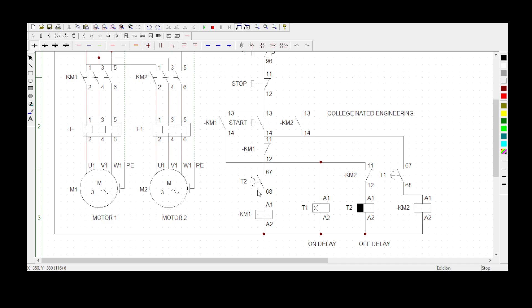When you press the start button, Motor 1 must start rotating immediately. There is a normally open contact of Timer 2 here. The delay-off timer works such that immediately when you energize it, its contacts change position at the same time. So when you press the start button, current flows, energizes Timer 2, and it immediately becomes normally closed — allowing KM1 to be energized so Motor 1 starts.